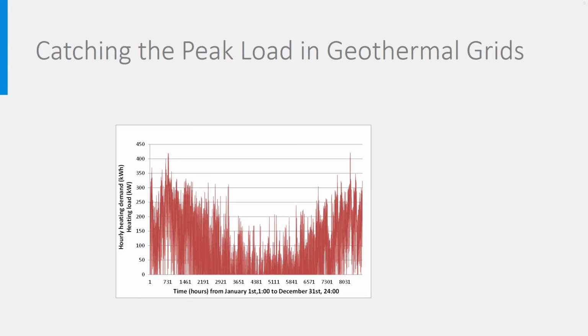What happens in geothermal grids is beyond this course on buildings' HVAC systems. However, as geothermal systems are expected to be more frequently used, it is worth realizing that buffering geothermal heat is an important issue. Geothermal plants are mostly designed to work year-round at constant load and cannot be controlled very easily. Geothermal pumps cannot be switched off that easily. They could be clogged and would not work anymore.